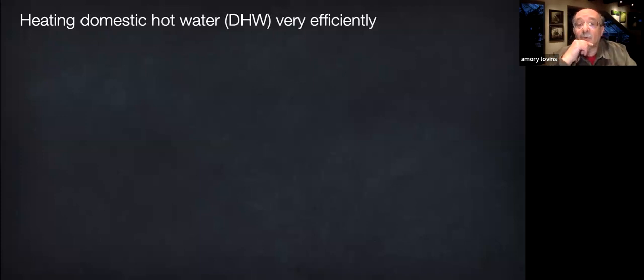In the Davis house you saw earlier, we heated the water with waste heat from the refrigerator freezer. And now home air to water heat pumps are widely on the market. Their coefficient of performance, COP, measures how much water heating they do per unit of electricity. A few years ago, 2019-20, the Energy Star best models could produce 40 Celsius water from 8 Celsius air with a COP of 3.5, from -8 Celsius air at 2.4, and from -15 Celsius air at 2, twice as efficient as a resistive water heater.